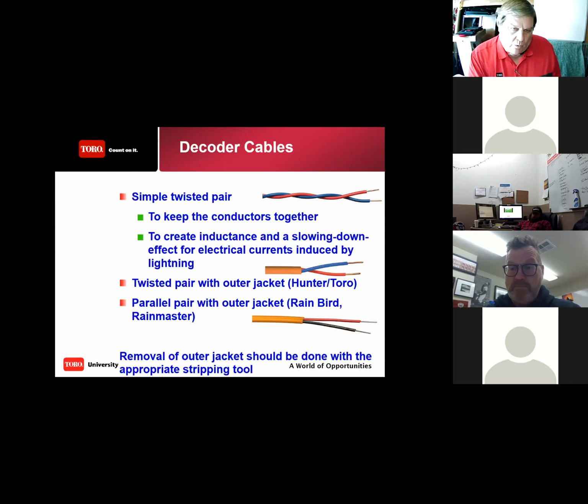So we have a wire path, and you've got communication on the wire path. Imagine driving your car on a boulevard. What happens to your radio when you go underneath the high power lines? You get static, or it loses your satellite signal. Well, you've got that same kind of noise, if you will, going down the two-wire path. If it's a twisted pair, that harmonic emission is retained closer to the wire itself. When they're laying flat parallel wire, the emission of that static noise is a little bit broader.